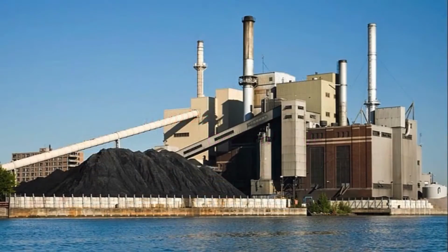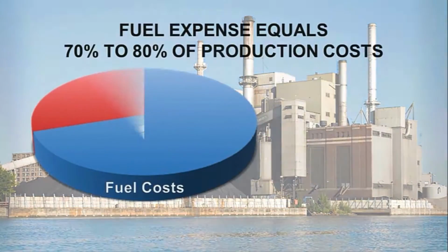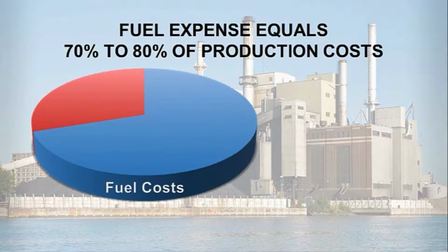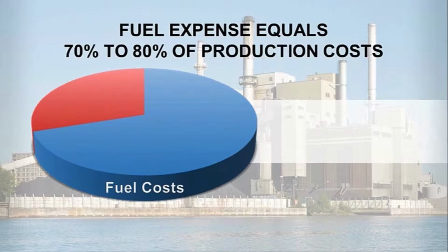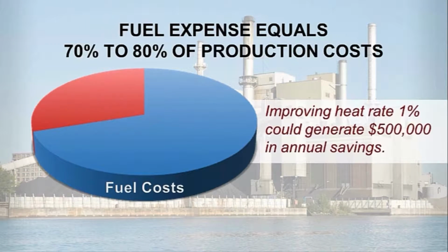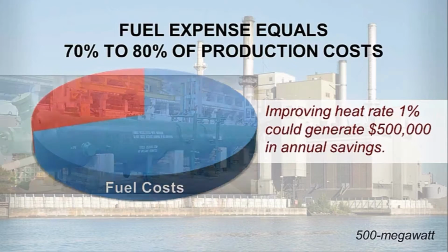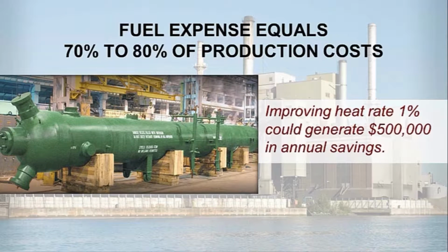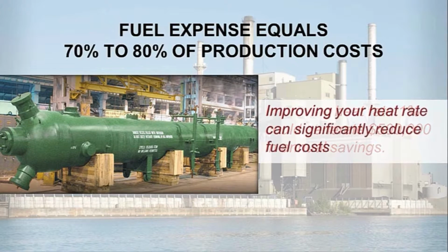For most power plant operators, fuel expenditures account for 70 to 80% of production costs and millions of dollars per year. In fact, improving heat rate 1% could generate $500,000 in annual savings for a 500-megawatt power plant. To contain fuel costs, power plants must maximize the efficiency of their feedwater heaters. That's why many companies today are focusing on improving heat rate as a way to use their feedwater heaters more effectively and significantly reduce their fuel costs.